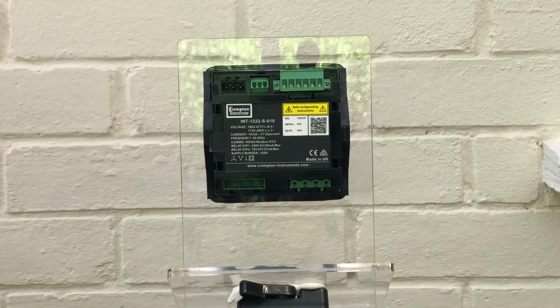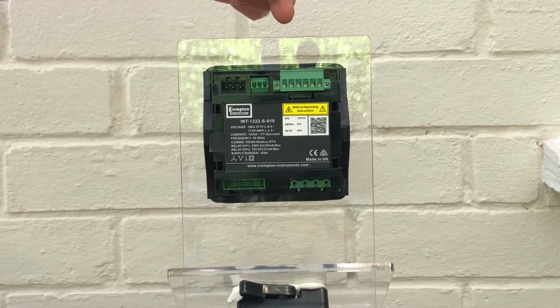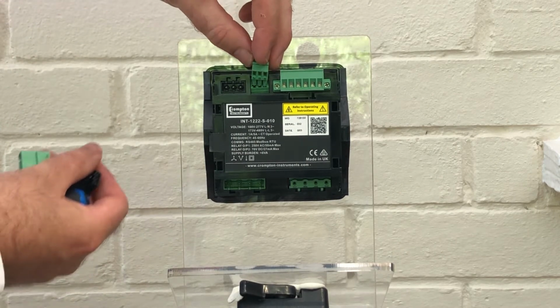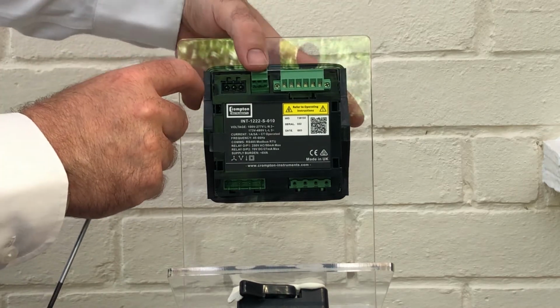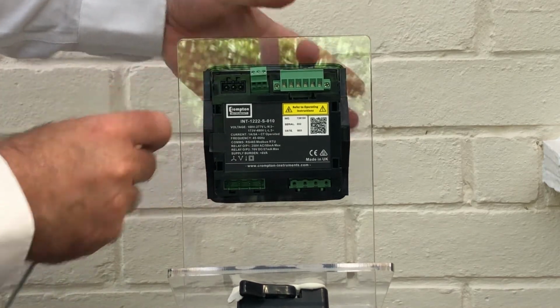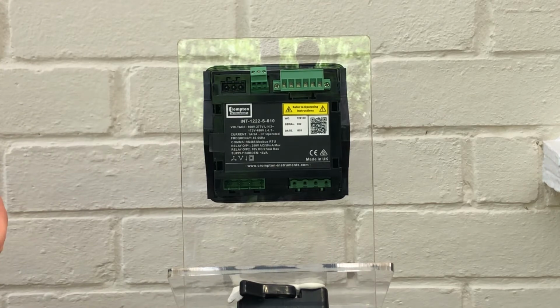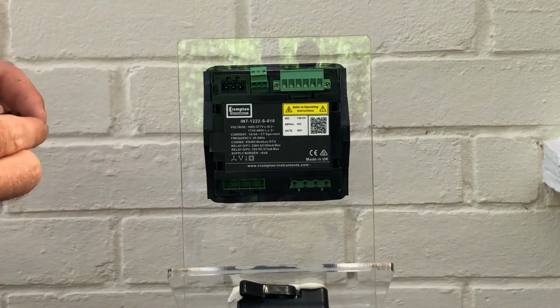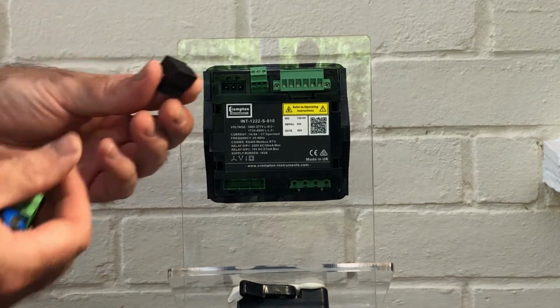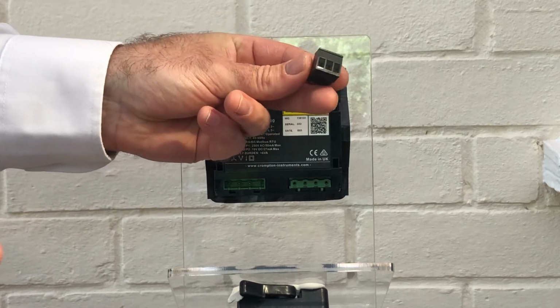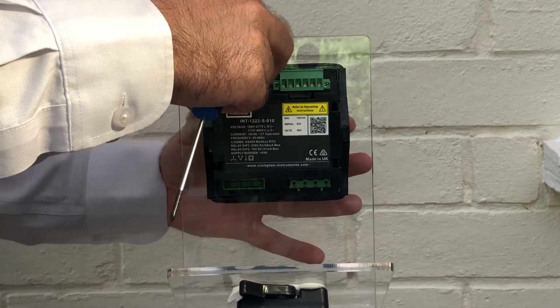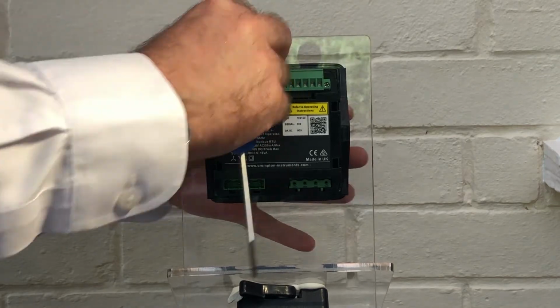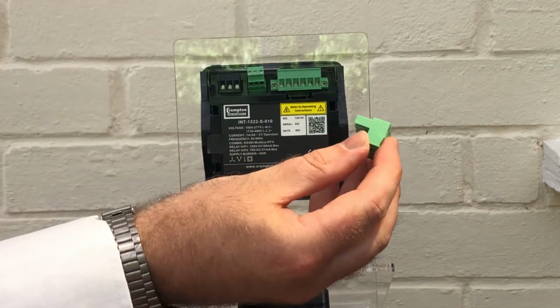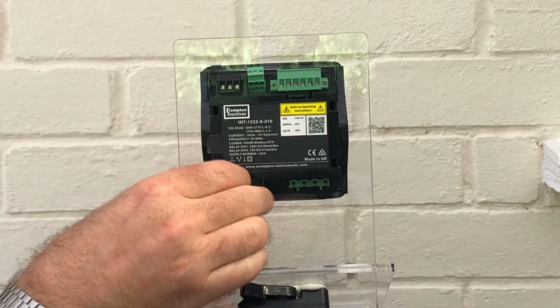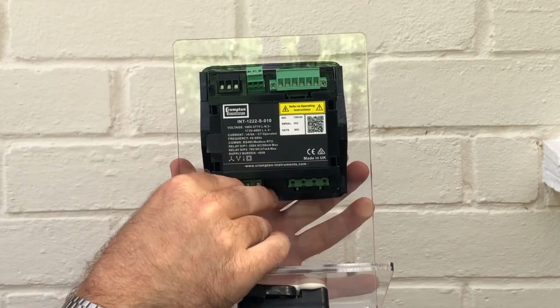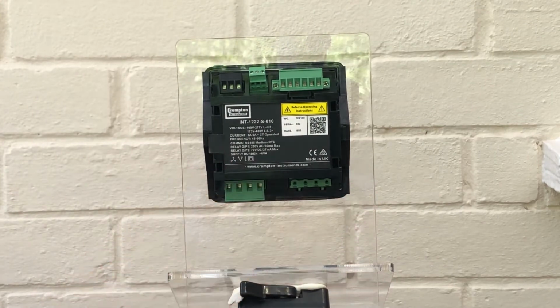Once the current terminal block is fixed into place, apply the Modbus communications terminal block into its socket. As this is the self-powered model, it comes with 2 pulsed relays as standard, and this is the block for the pulsed relays. Applied here. And finally, the voltage terminal block fits on the bottom of the product like so.